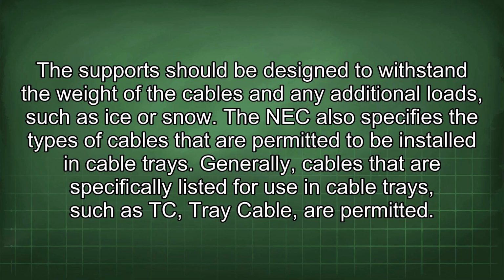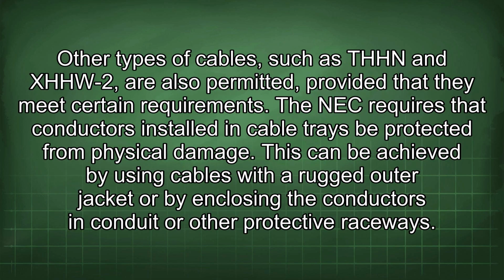The NEC also specifies the types of cables that are permitted to be installed in cable trays. Generally, cables that are specifically listed for use in cable trays, such as TC tray cable, are permitted. Other types of cables, such as THHN and XHHW-2, are also permitted, provided that they meet certain requirements. The NEC requires that conductors installed in cable trays be protected from physical damage.